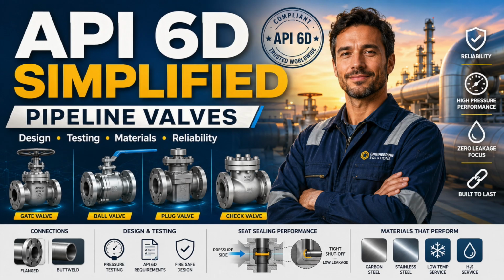A valid test certificate can still prove the wrong performance for your application. Quality assurance should therefore be risk-based. Material verification, welding qualification, non-destructive examination, dimensional checks, pressure testing, seat testing, functional testing, actuator stroke, coating inspection. Documentation. Witness the things that cannot be verified later.